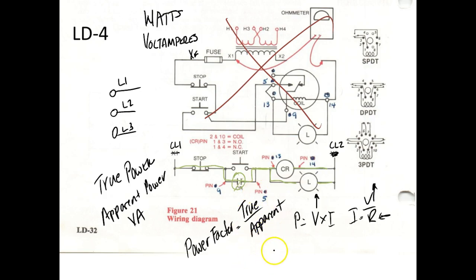If I took this and multiplied it by 100, it would be a percentage. Alabama Power charges a penalty if you're not running a power factor of 0.95. If you run a power factor of less than 0.95, you pay a penalty. I don't know about TVA. You'd think they would be happy about that because you're paying for something you're not getting. But what you've got to understand is the power grid has got to be able to provide apparent power. So you've got all this wasted power out there. That means Alabama Power is going to have to use bigger transformers and bigger conductors to handle that apparent power. So that's what they do.